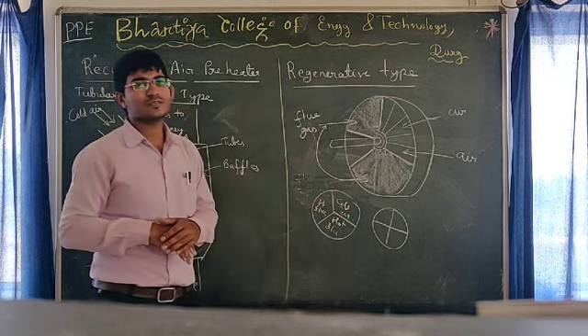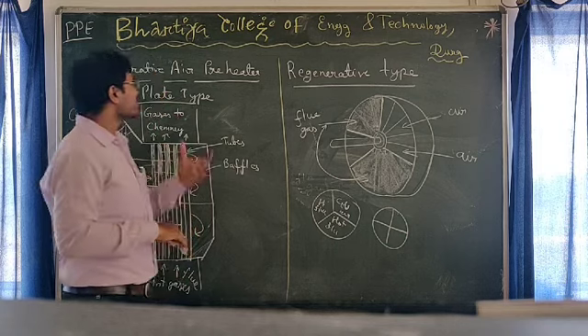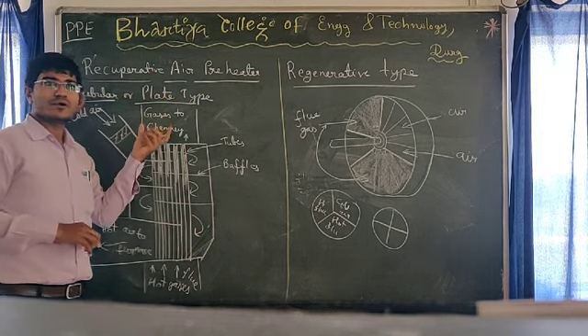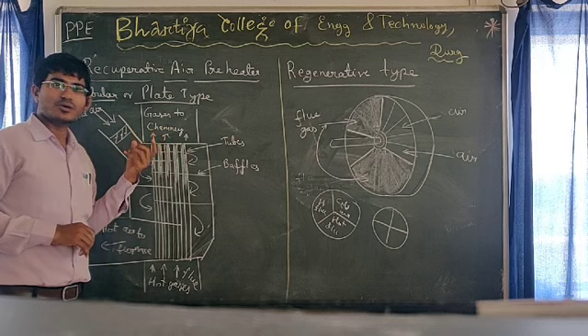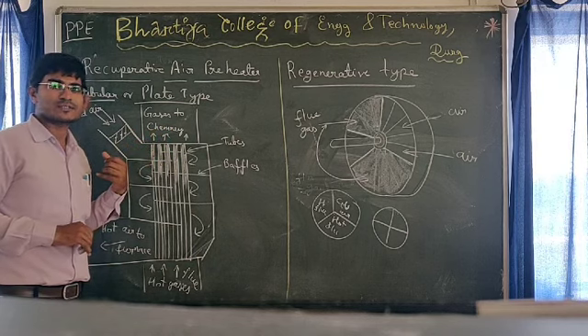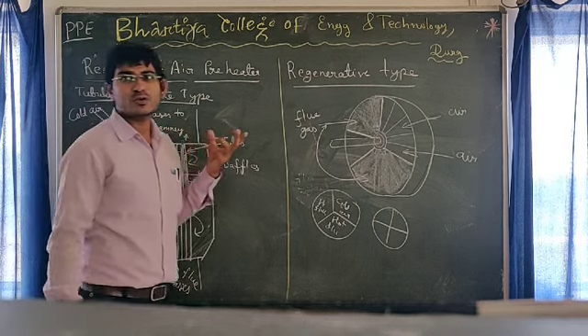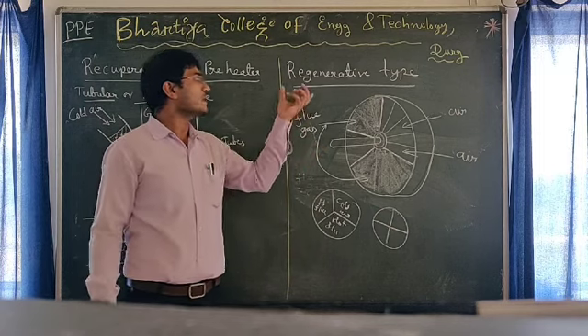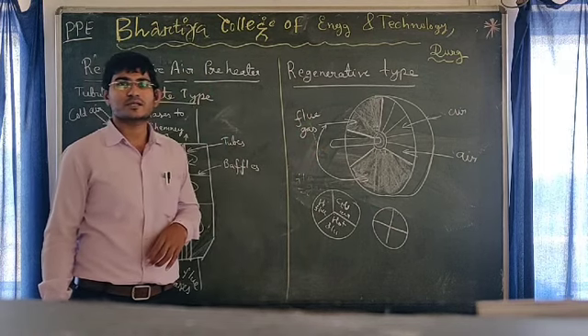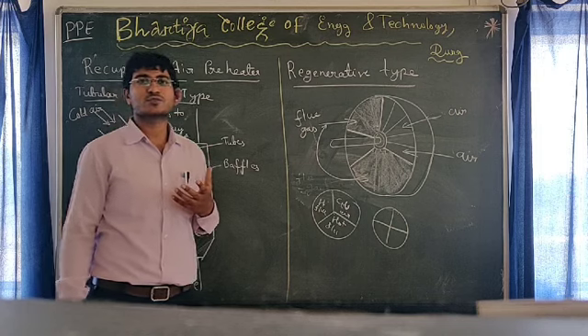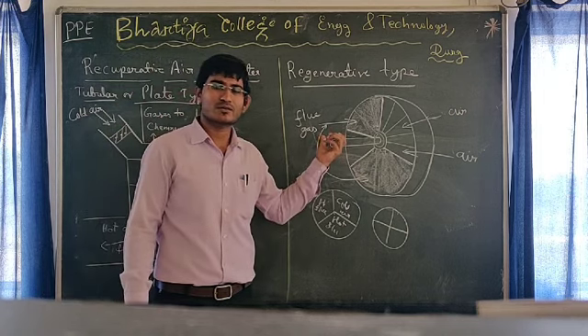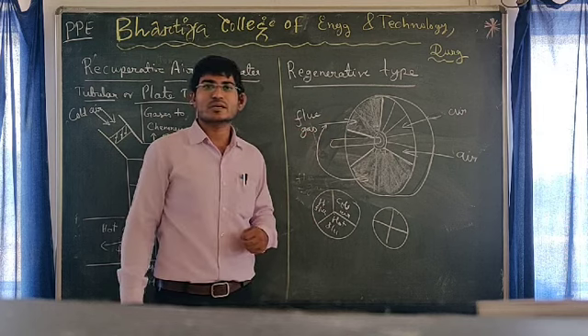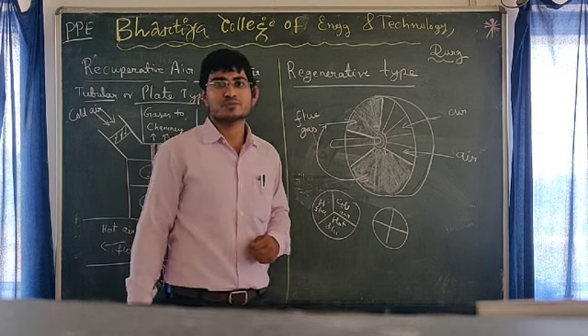Hence its name: regenerative air pre-heater. Recuperative air pre-heaters are used in boilers in power plants having low load or less load capacity. In high load capacity power plants, we use the regenerative type air pre-heater. Nowadays, in supercritical boilers, we are using this regenerative type air pre-heater. Thank you.